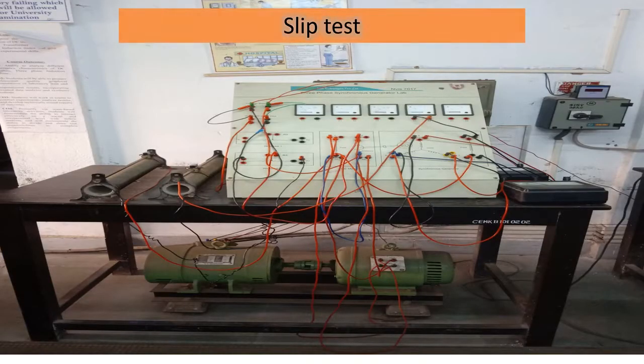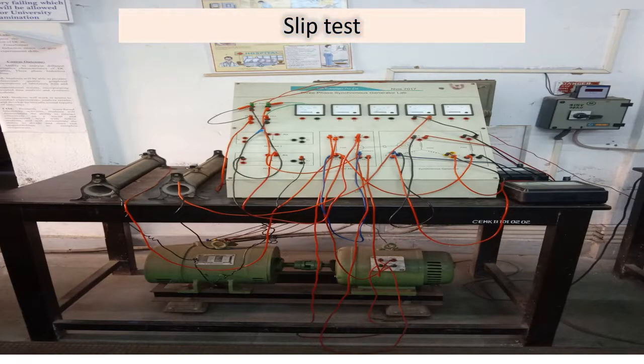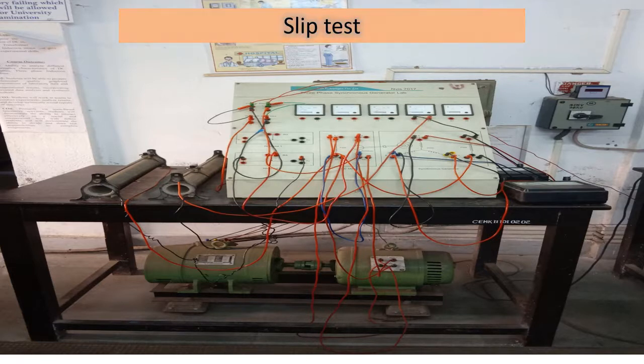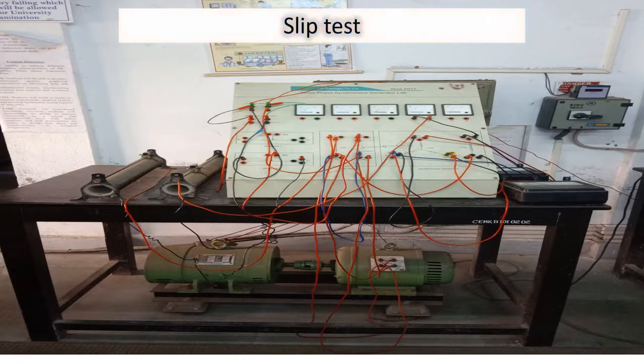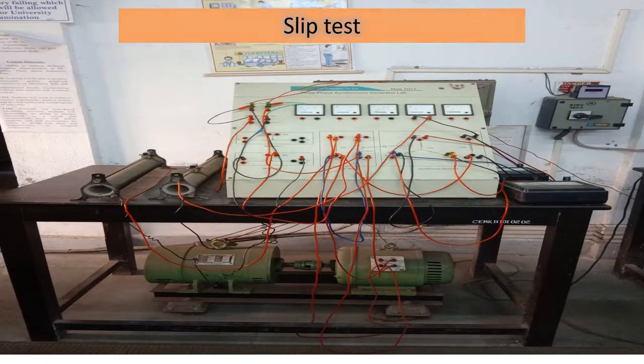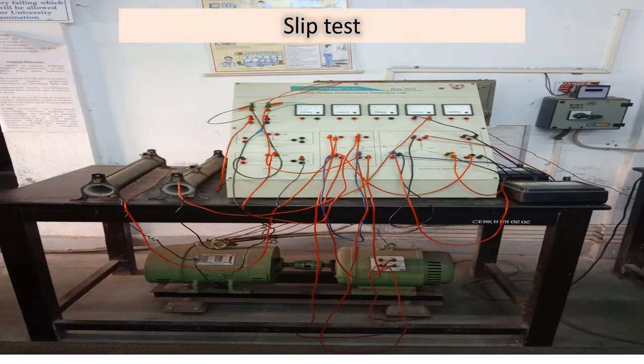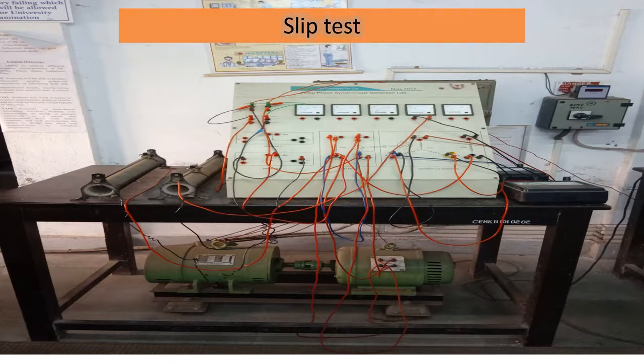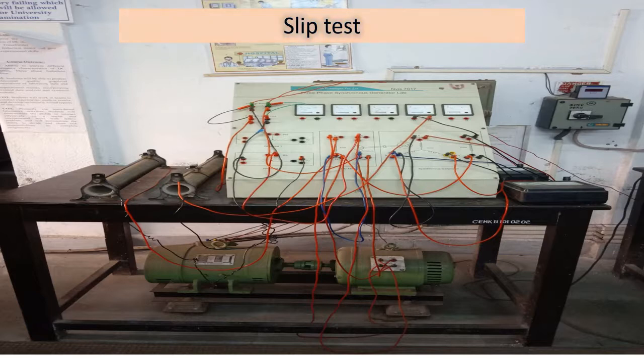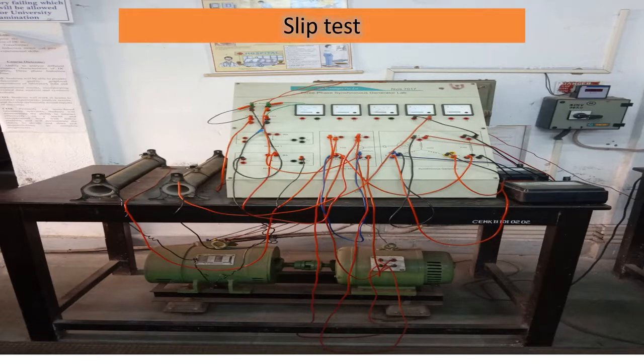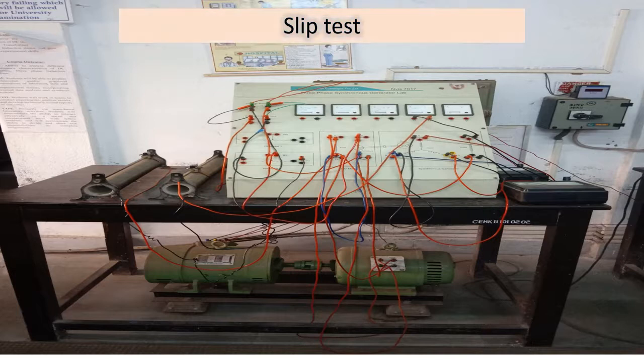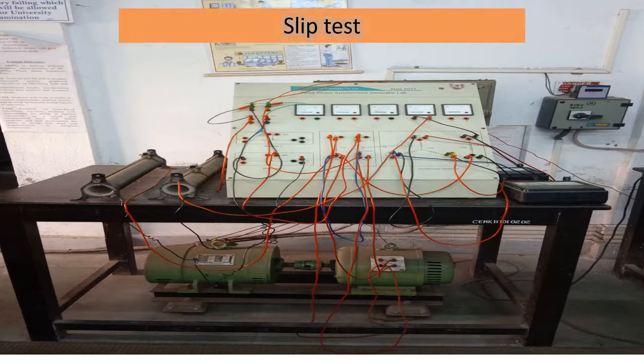This is the experiment of slip test on a salient pole synchronous machine. The objective is to determine the direct axis reactance XD and quadrature axis reactance XQ. With the oscillation of stator current, the applied voltage also oscillates a little in reverse order between some minimum and maximum. Thus, taking advantage of slip condition, the direct axis reactance XD and quadrature axis reactance XQ as offered by the salient pole synchronous machine can be found out easily.